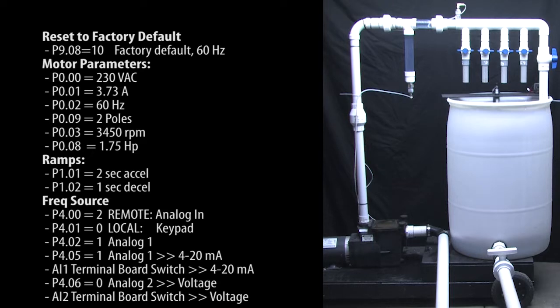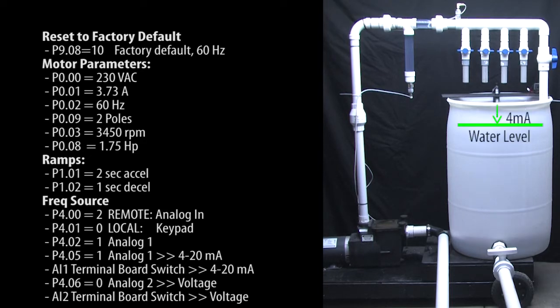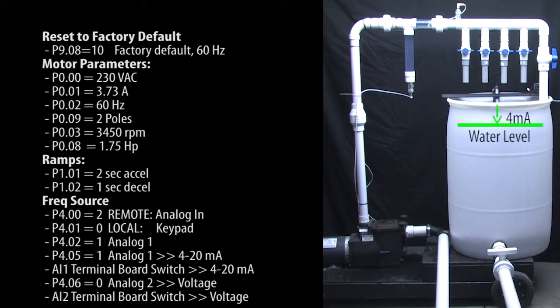For Sleep Mode 1, we have the ultrasonic sensor set to provide 20 mA down here and 4 mA up here. So the sensor is telling us how empty the tank is, not how full it is. The fuller the tank gets, the smaller the sensor signal will be.